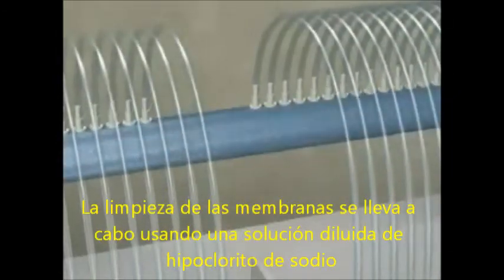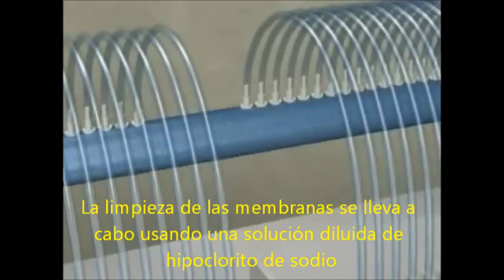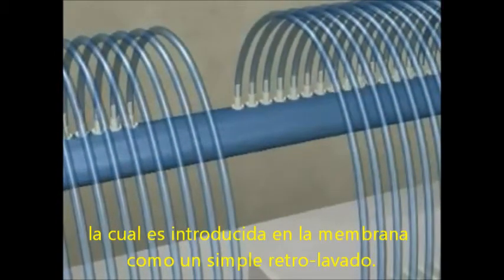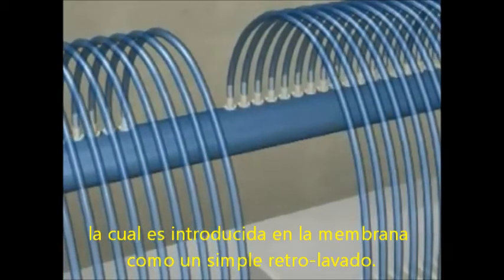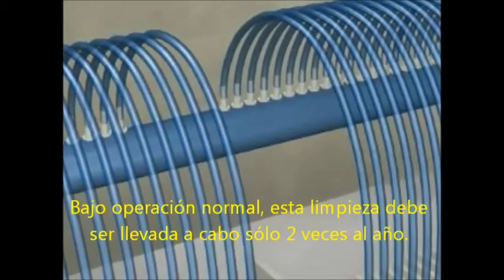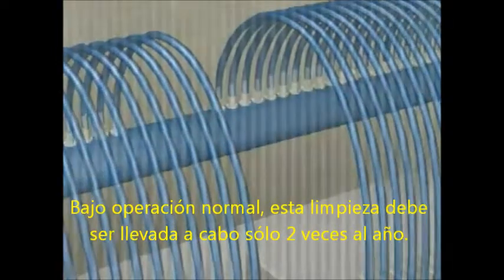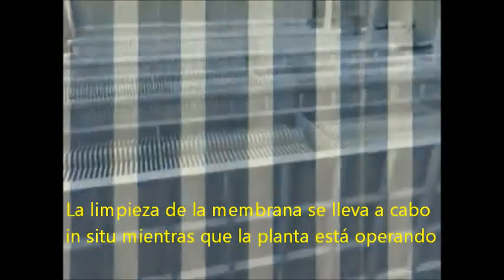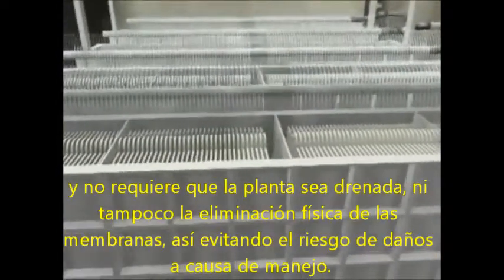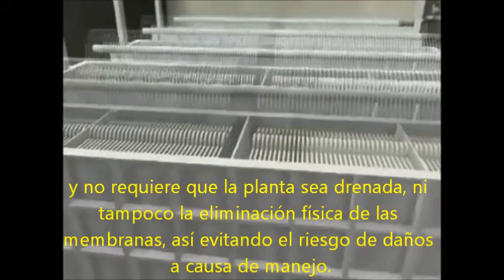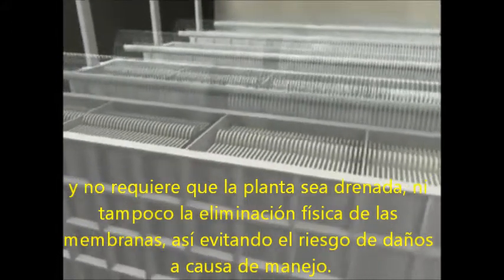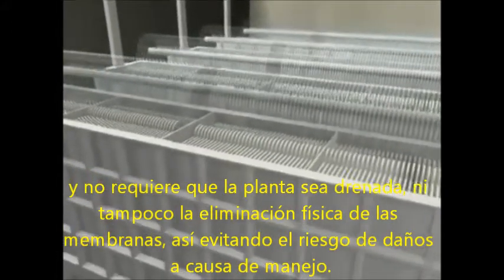Cleaning of the membranes is undertaken using a dilute sodium hypochlorite solution, which is introduced into the membrane as a simple backwash. Under normal operation, this cleaning need only take place twice a year. There is no need for continuous automated back flushing, which increases complexity and requires significant chemical usage. Membrane cleaning is conducted in situ while the plant is operating and does not require the plant to be drained down or the physical removal of the membranes, thus avoiding risk of damage in handling.